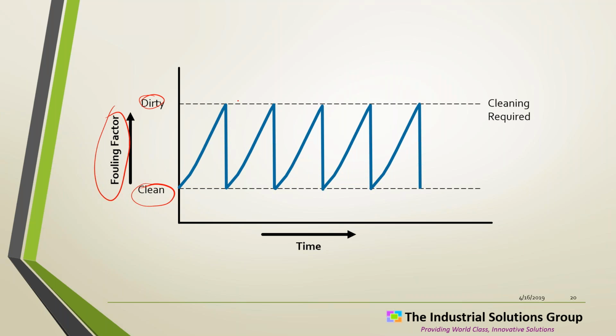And when it gets to that point, it's time to shut down the process for a while, and you'll clean it. You could rod out the tubes, or a lot of times it's an acid wash or something that cleans the tubes. What we're showing here is that you've got to do it. It's just part of the ongoing operation, something process people deal with all the time with their heat exchangers.